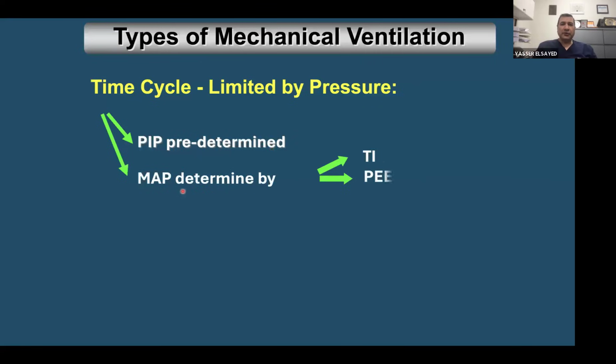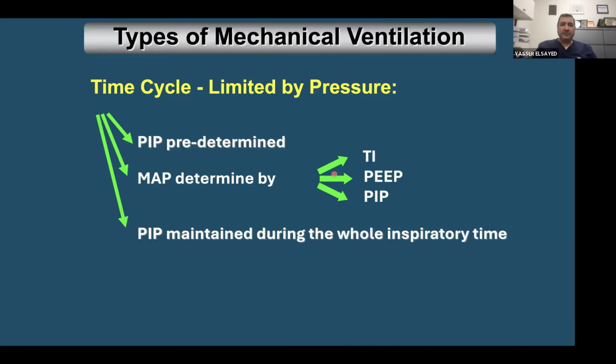And then the mean airway pressure is calculated based on your I time preset, PEEP preset, and PIP. You preset that on the ventilator yourself. So the mean airway pressure is the area under the curve for the I time, with PEEP as a baseline, and PIP. And PIP is maintained during the whole inspiratory time. Just please focus with me on this point. Why are we not using volume limited ventilation in neonates? As I will show in the graph, neonates, especially premature infants, don't have enough capacity to create their own I time. So we don't allow the I time to be determined by the patient. In a premature infant breathing through a small tube, this is very tough to happen.